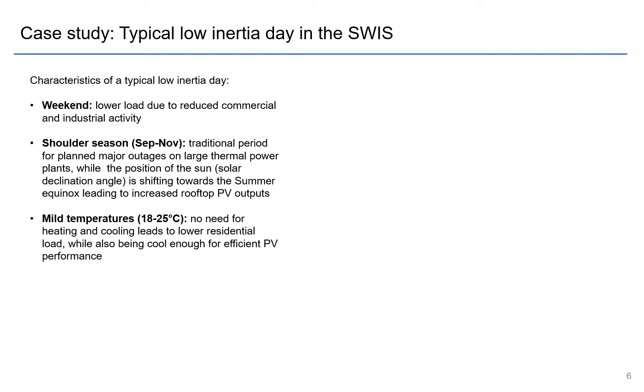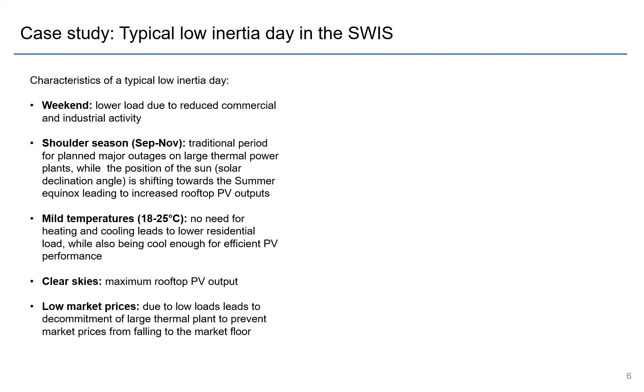Around this time of year, temperatures are very mild — 18 to 25 degrees Celsius — so there's little need for heating or cooling in residential loads, and cooler temperatures also benefit rooftop PV efficiency. On your lowest inertia days, you always have clear skies giving maximum PV output. Finally, because of low loads there are low market prices, which incentivizes large thermal plants to decommit to avoid prices falling too low. This withdrawal of synchronous generation further reduces inertia during these decommitment periods.